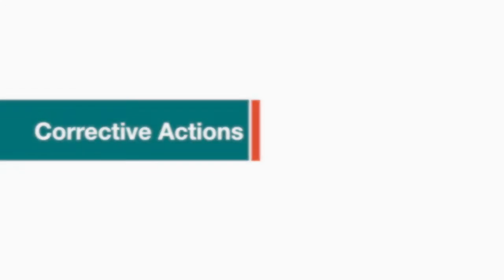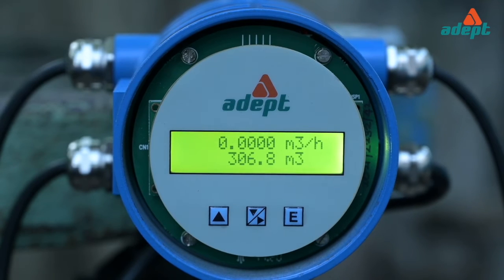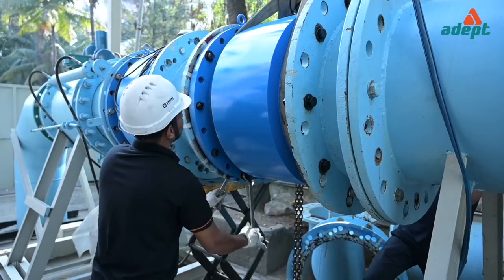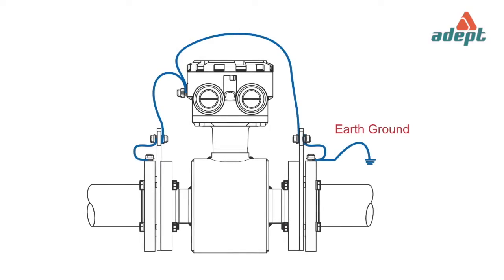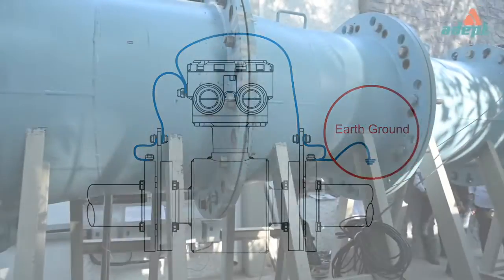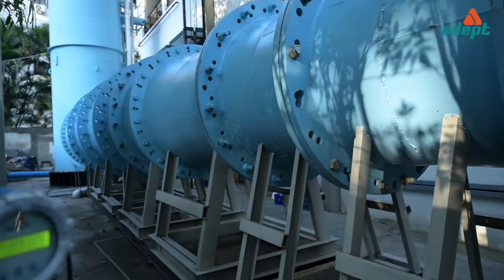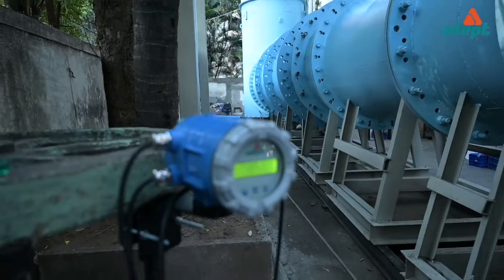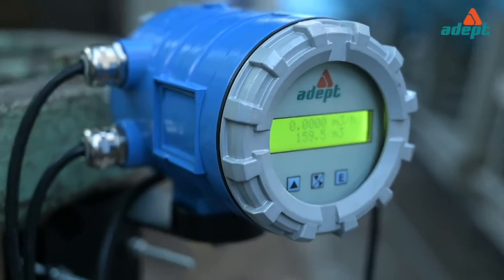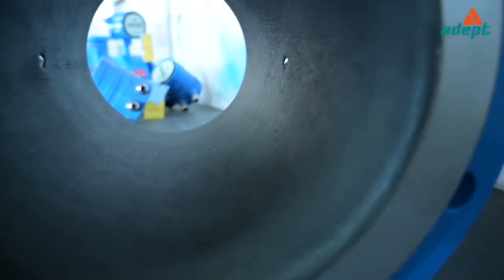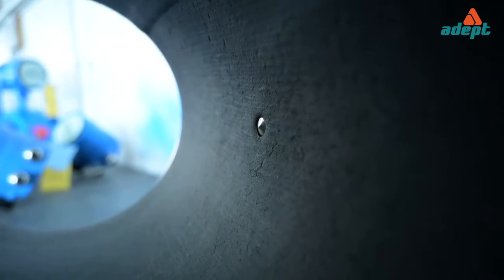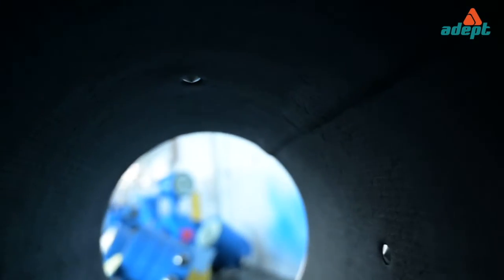Corrective actions: ensure absolute zero flow and check. Mount the flow tube correctly and check. Perform grounding as instructed and check. Ensure that the flow tube has been mounted to ensure full bore and then check. Isolate and remove the flow tube; remove any deposit on and around the electrodes.